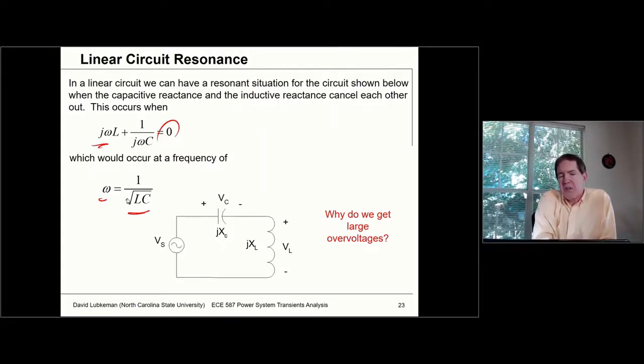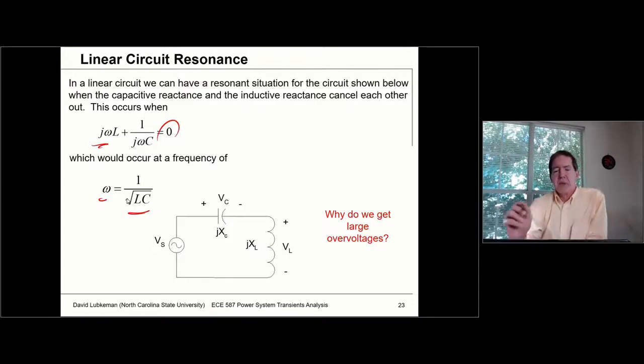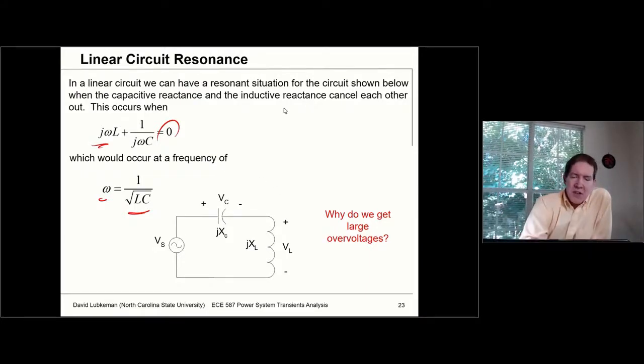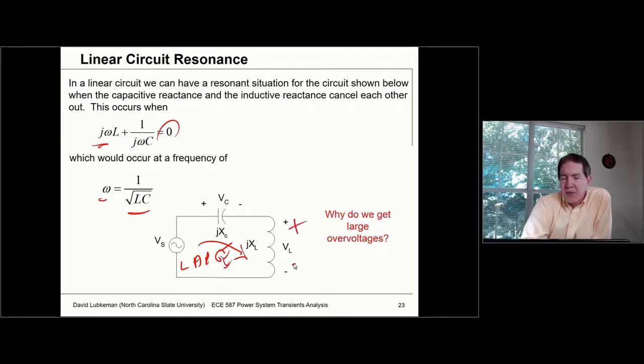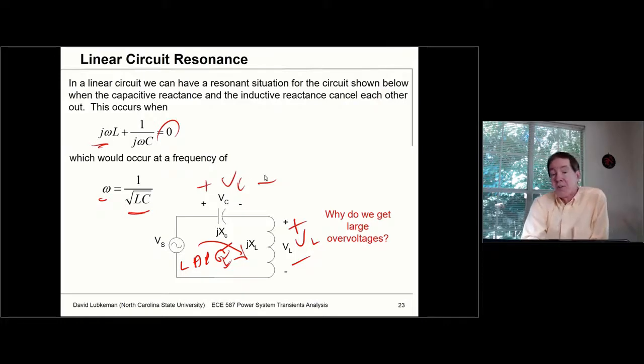The issue is that this interaction can occur at frequencies you actually encounter in practice. Because if you have series resonance, this is going to cause a large current flow. And whenever you have a large current flow, it's going to cause a large value of voltage across the inductance and also a large value of voltage across the capacitance. What we're more concerned about, since the inductance usually dominates, is this particular overvoltage.